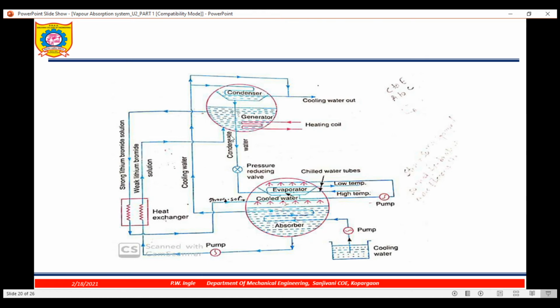Now see, this weak solution is supplied. Weak solution means what? It consists of lithium bromide and water. This will be pumped back to the generator. Okay. Now the strong solution which is coming from the generator will give its heat to the weak solution. So some heat will be used over here, so some amount of heat can be saved. Okay.